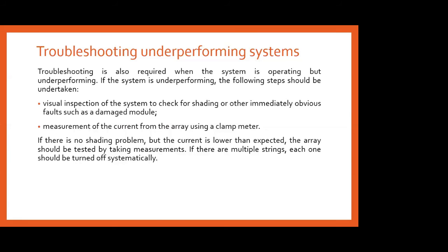Once the faulty string has been identified, the circuit breakers or the fuses should be checked for failures. If they have not failed, then we can continue with fault finding on the PV arrays. So we have to check for the shading, that is, a complete visual inspection has to be done.